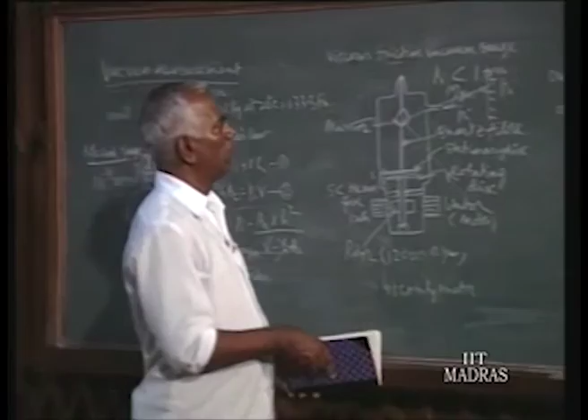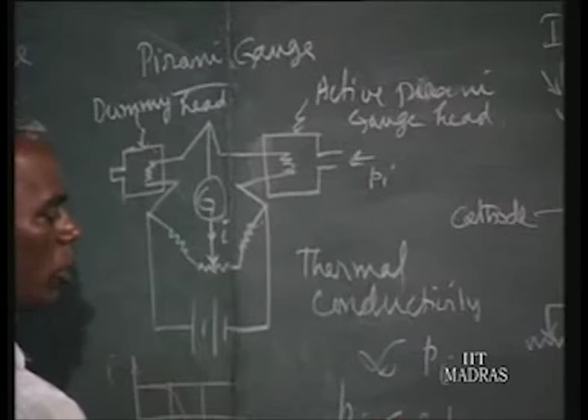And this another one, this is thermal conductivity. This Pirani gauge is based upon thermal conductivity. Thermal conductivity is again proportional to pressure, when the pressure is less than 0.1 torr. This is the physical property that is made use of there.